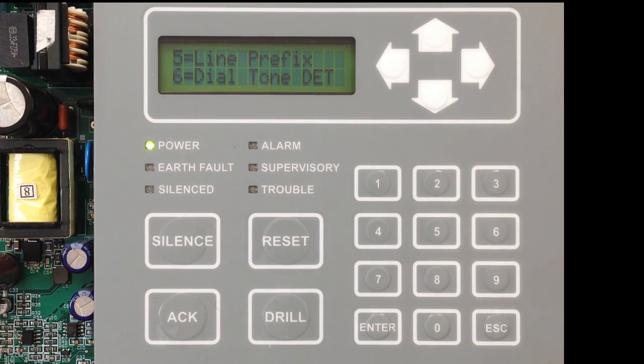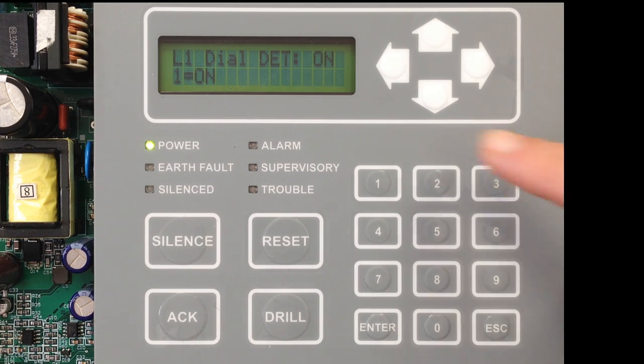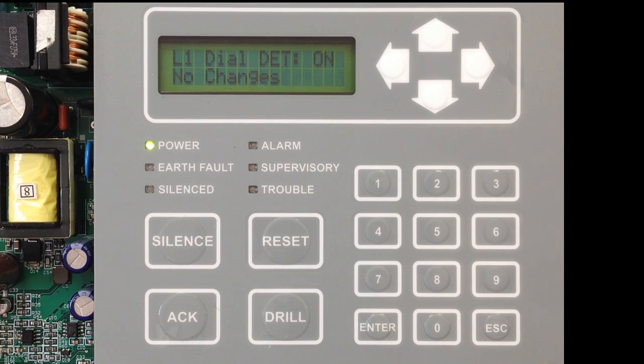The last option in Line 1 Setup is Dial Tone Detect. This is going to enable or disable the detection of dial tone for Line 1. Going into option 6, it is currently detecting for dial tone. So when the dialer is active and it seizes the phone line, it's going to look for dial tone — if there is no dial tone, it's going to think the line is bad. You can disable that by selecting option 2 to turn it off.